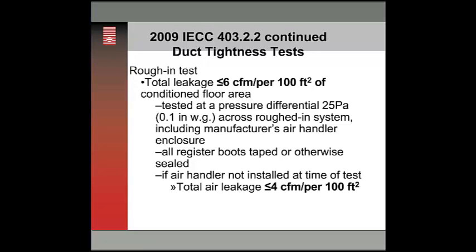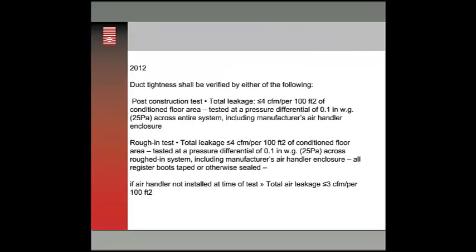Under the 2009 at rough-in, your number is 6%. If there's no air handler installed at the time of test, 4%, 4 CFM per 100 square feet.